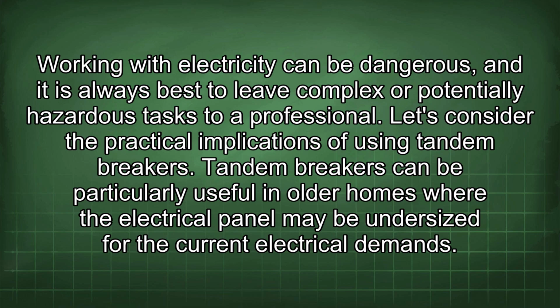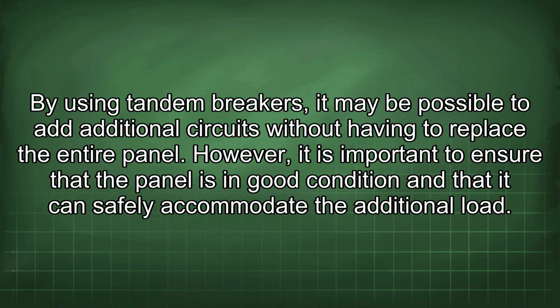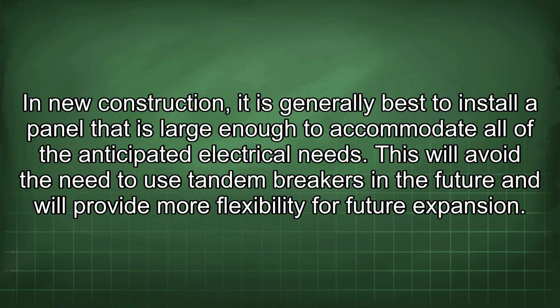Let's consider the practical implications of using tandem breakers. Tandem breakers can be particularly useful in older homes where the electrical panel may be undersized for the current electrical demands. By using tandem breakers, it may be possible to add additional circuits without having to replace the entire panel. However, it is important to ensure that the panel is in good condition and that it can safely accommodate the additional load. In new construction, it is generally best to install a panel that is large enough to accommodate all of the anticipated electrical needs. This will avoid the need to use tandem breakers in the future and will provide more flexibility for future expansion.